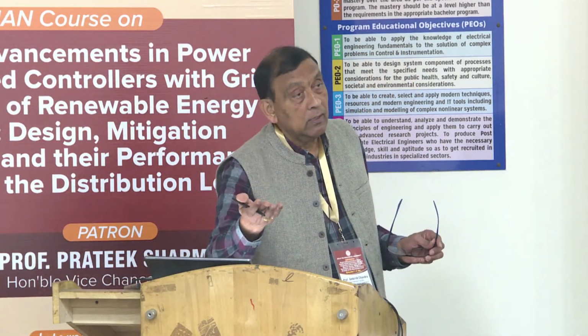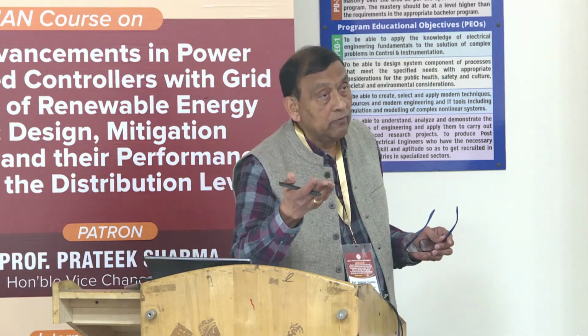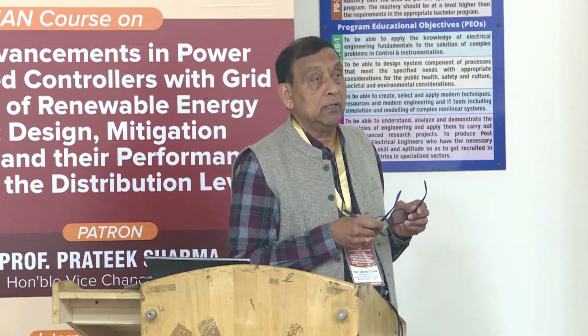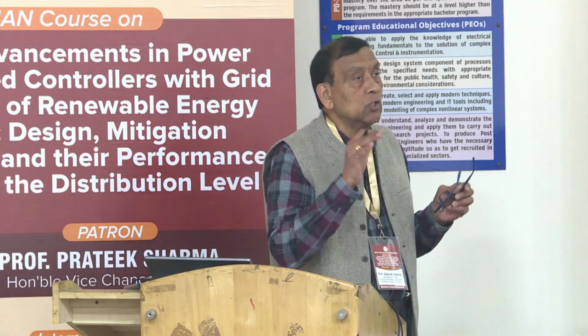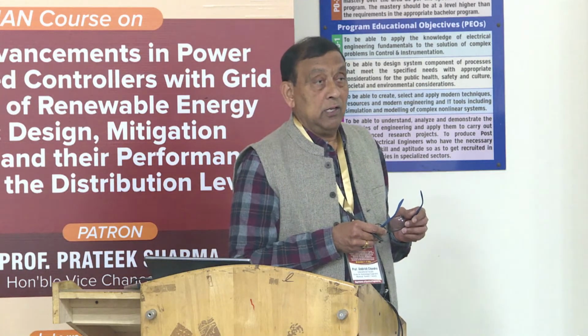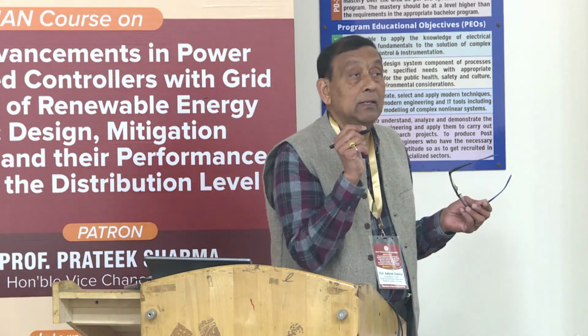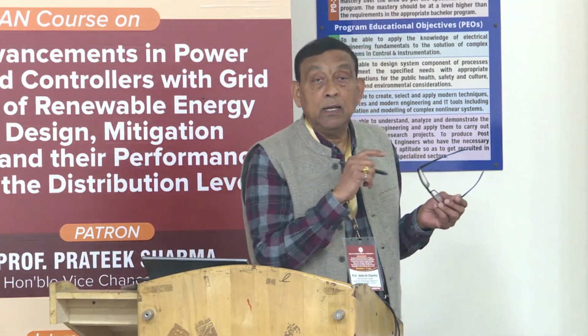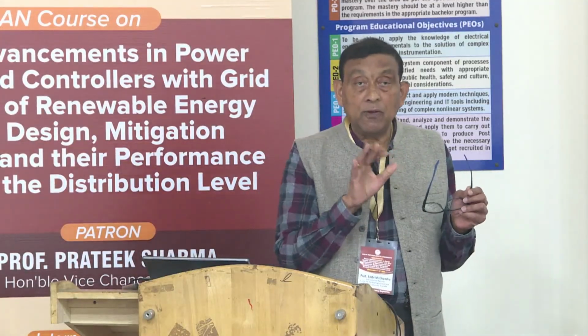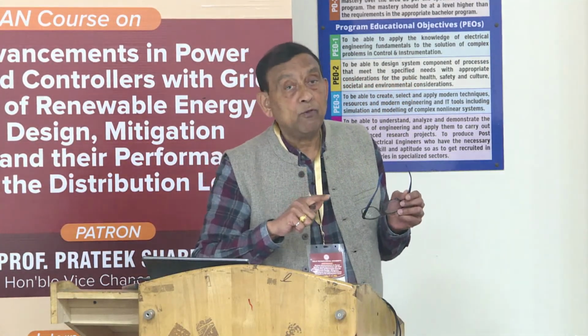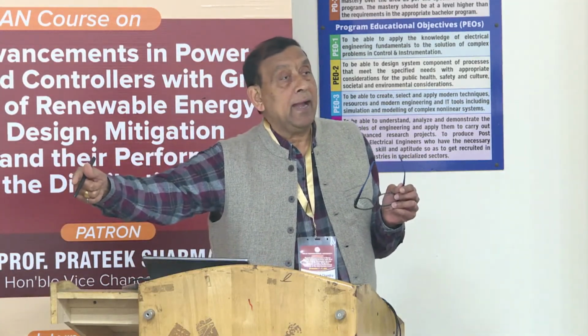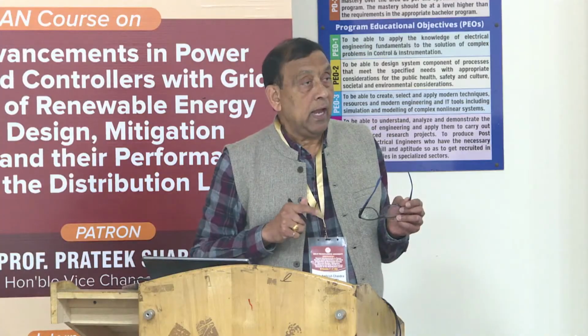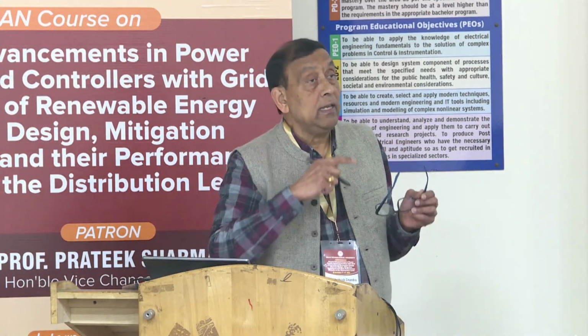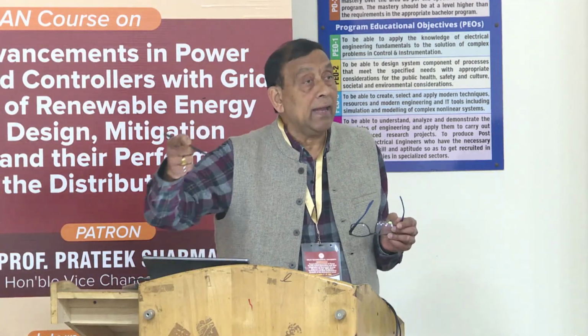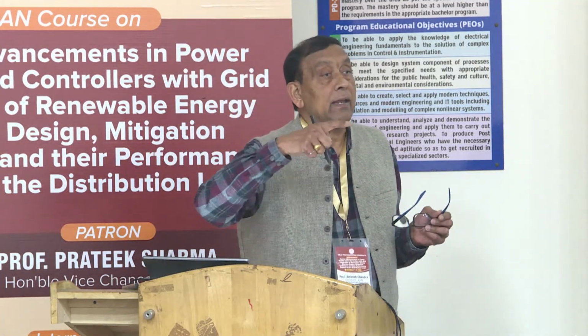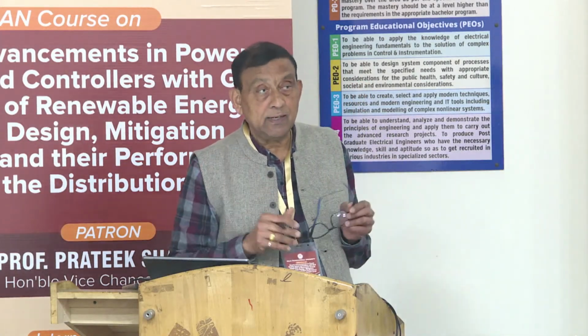And seventh harmonic, fifth harmonic. If you are having a fifth harmonic, you see the eddy current losses are proportional to the square of the frequency. So it means whatever eddy current losses you are having with the fundamental frequency, you will have 25 times more eddy current losses if you have a fifth harmonic. And if you have a seventh harmonic, then the eddy current losses will be 49 times more than what you are having at fundamental frequency. So this is a very serious thing.